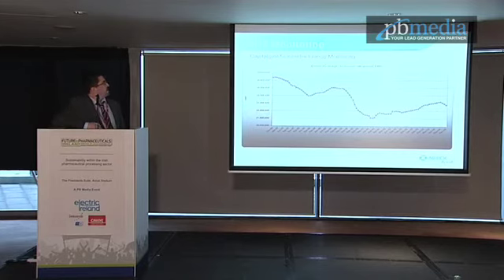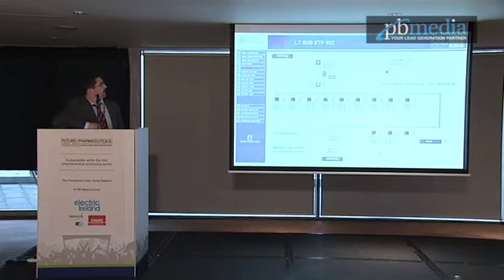Okay, so here's an overview of our electricity monitoring system. It was installed for energy efficiency, which it did, saved 6 gigawatt hours there over a couple of years. The increase here on the right hand side is due to increase in production. That's a quick overview of the system that we put in. When we installed the system for energy reduction, we also installed it to alert for power quality issues or power factor on the system, which has proved to be very beneficial.